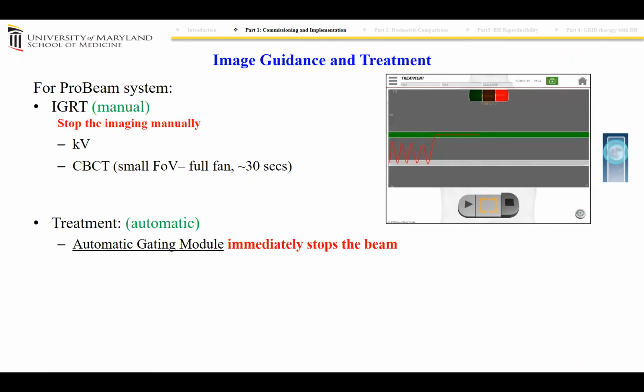So during the treatment for the IGRT, again, is similar to CT. We have to stop the imaging manually if the patient goes out of the breath hold level, but the treatment is completely automatic. So we usually start the beam and then wait for the patient to go to the breath hold. As soon as the patient gets to the breath hold, the beam runs, and then as soon as the patient goes out of the breath hold, it stops automatically.